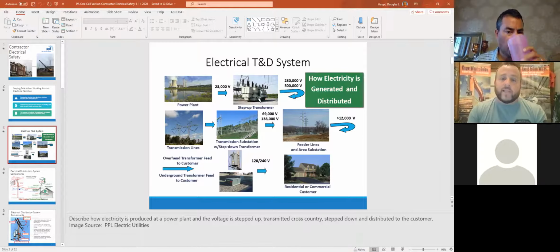Then we take it to a transmission substation where we got to bring it down to a more manageable level where we have similar transformers to this. And these transformers then work the opposite direction, and we step it down from 230 and 500, down to 69 and 138,000 volts of electricity.